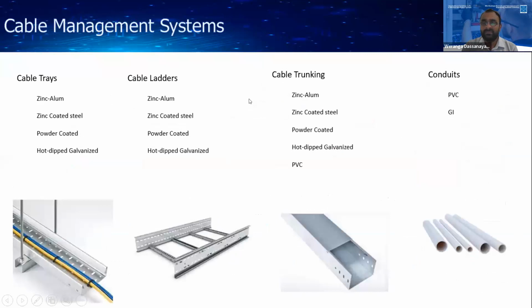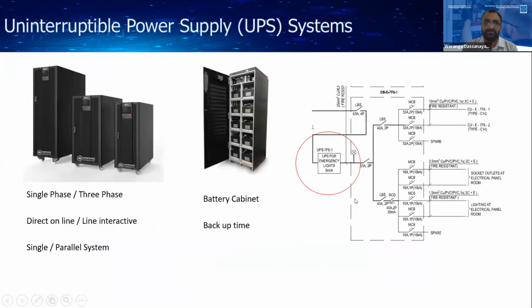These are some cable management systems. I think I already explained this cable management system type to you because this is very important. When you are putting cables in a cable management system, the current carrying capacity will be different for the same cable if you are using a different kind of management system. For the same cross-sectional cable, if you are putting it in a cable tray, a cable ladder, or a cable trunking, the current capacity is different. Therefore, you have to clearly see where these cables are installed.